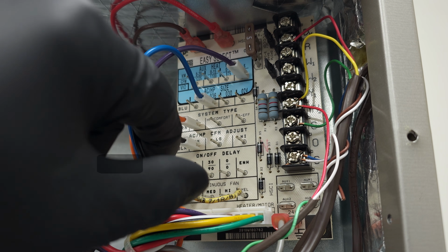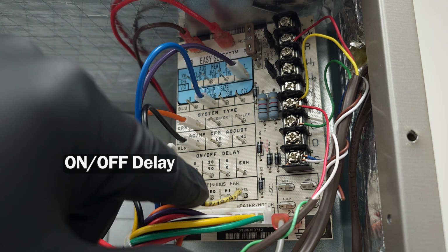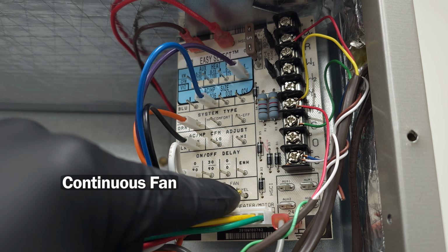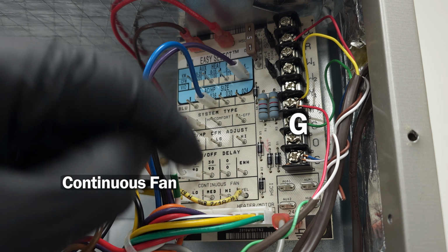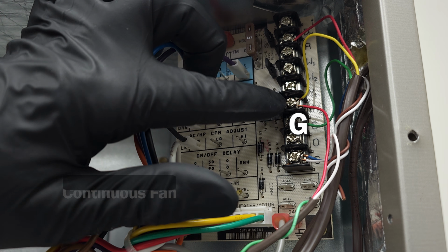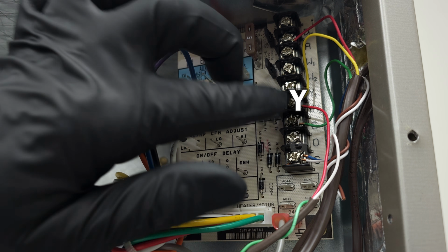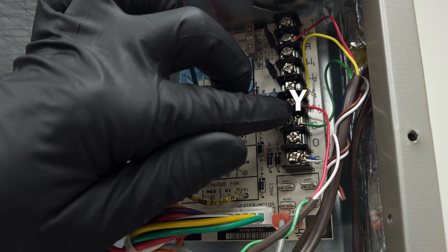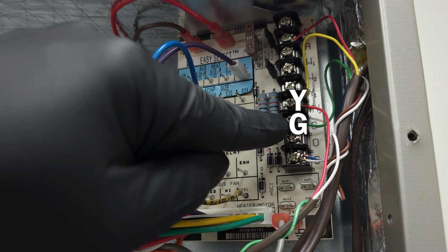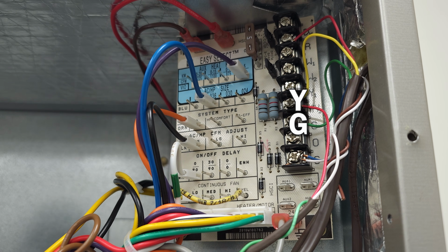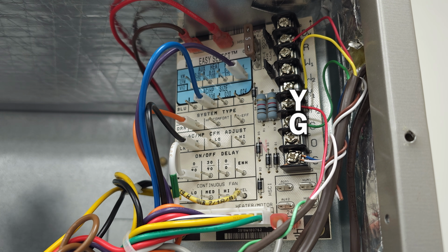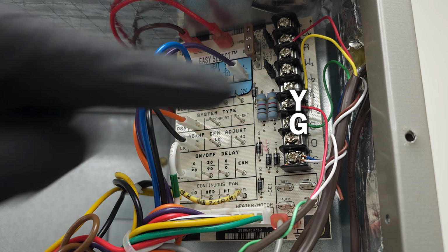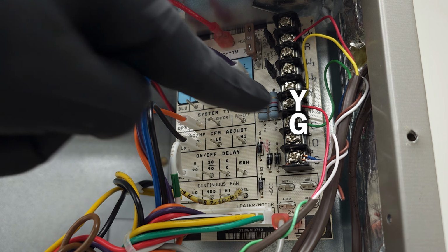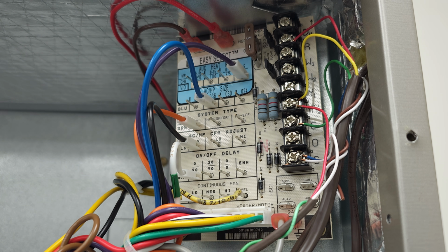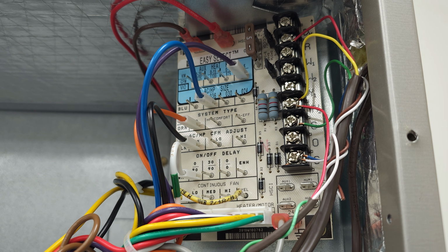And the on-off delay, that doesn't have to do with this CFM issue. And the continuous fan, that's only if you just are powering the G terminal right here. But during air conditioning mode, we're actually powering the Y. And so anytime the Y is powered, you're going to also be most likely powering the G as well on a circuit board like this, based on the thermostat that you have. But that's going to turn on the outdoor compressor and the indoor fan motor. And so it'll turn it on at its higher fan speed when you have 24 volts on the Y terminal. So we're going to go ahead and put this cover back on, and we're going to check the CFM again.